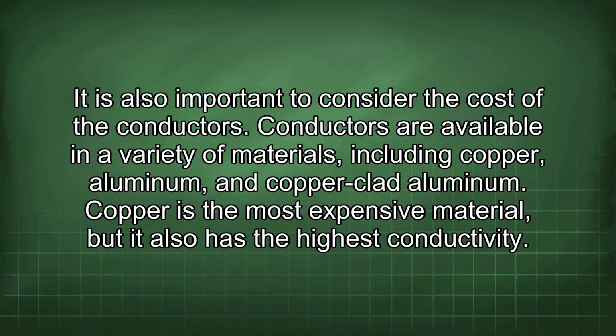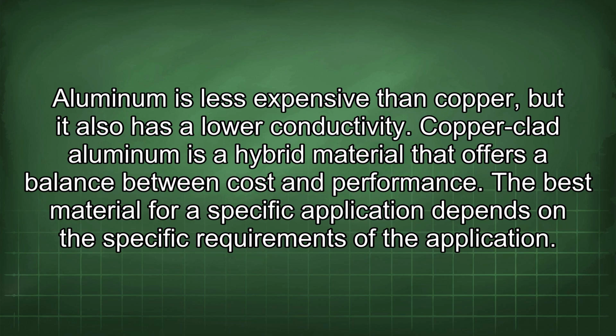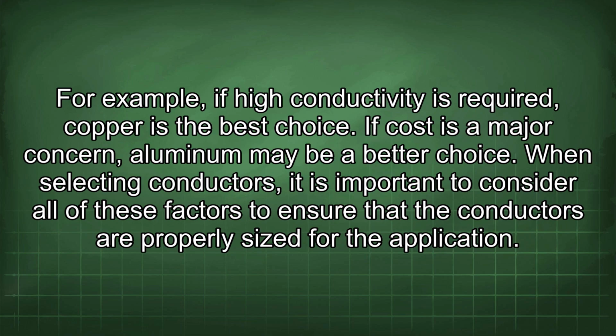It is also important to consider the cost of the conductors. Conductors are available in a variety of materials, including copper, aluminum, and copper-clad aluminum. Copper is the most expensive material, but it also has the highest conductivity. Aluminum is less expensive than copper, but it also has a lower conductivity. Copper-clad aluminum is a hybrid material that offers a balance between cost and performance. The best material for a specific application depends on the specific requirements of the application. For example, if high conductivity is required, copper is the best choice. If cost is a major concern, aluminum may be a better choice.